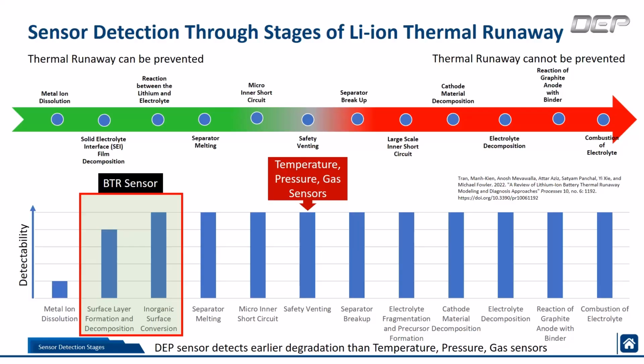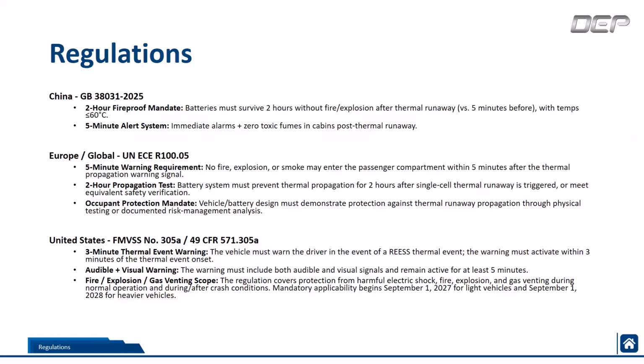So knowing this is important. Now, due to this, we also have regulations that occur from the thermal runaway. So we have current regulations in China where it says the batteries must survive 2 hours without any fire or explosion after thermal runaway, or 5 minutes before with temperatures less than or equal to 60 degrees Celsius.